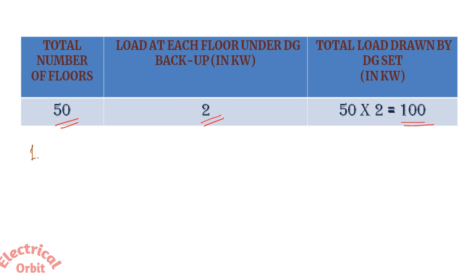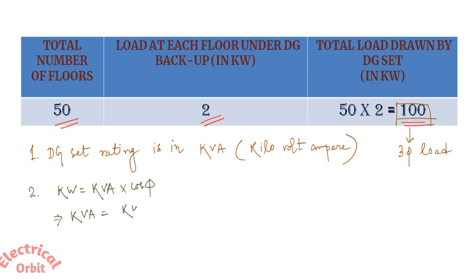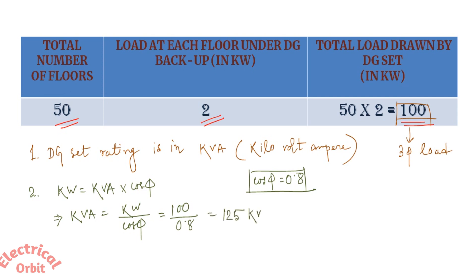The most important thing to remember is that DG set rating is in KVA (kilovolt-ampere). This 100 kilowatt load is your total three-phase load. The relationship is: kilowatt = KVA × cos φ, so KVA = kilowatt ÷ cos φ. The standard value of cos φ is 0.8. Therefore, 100 kW ÷ 0.8 = 125 KVA.